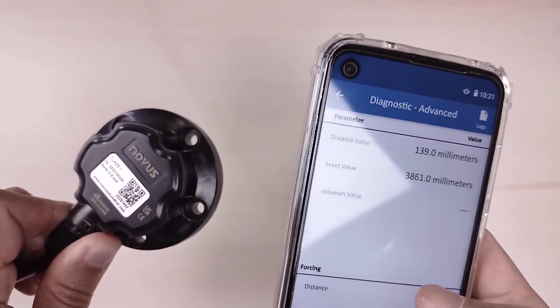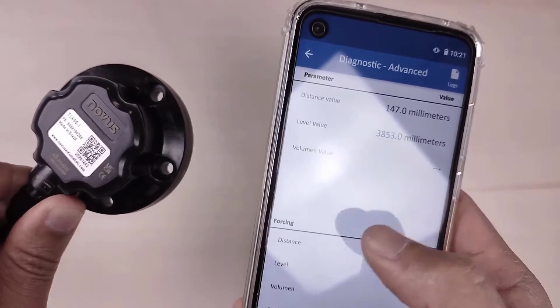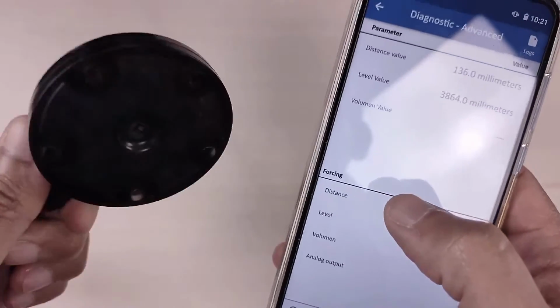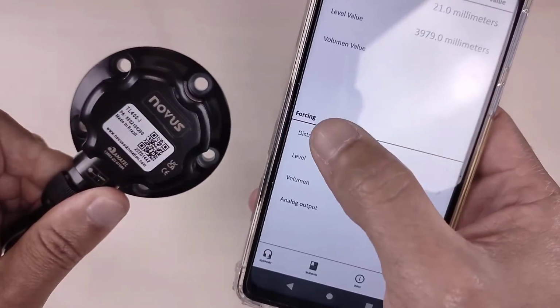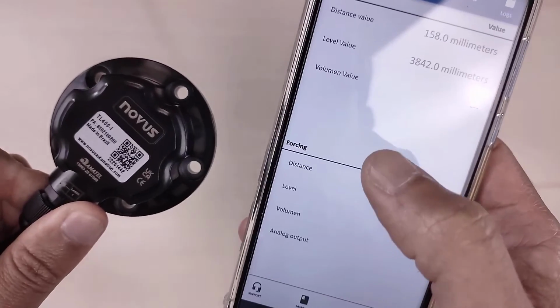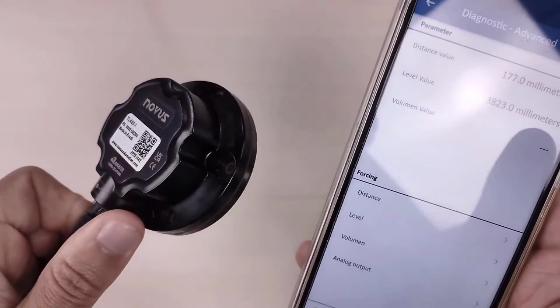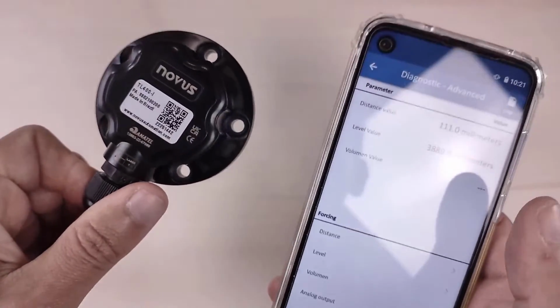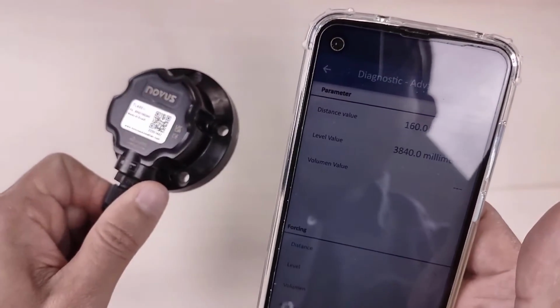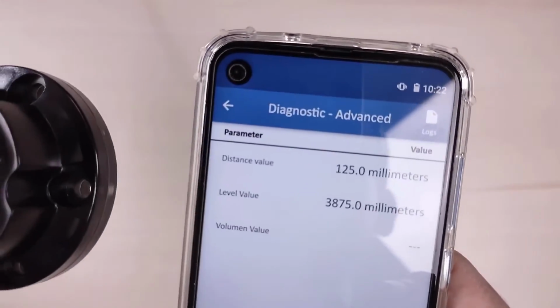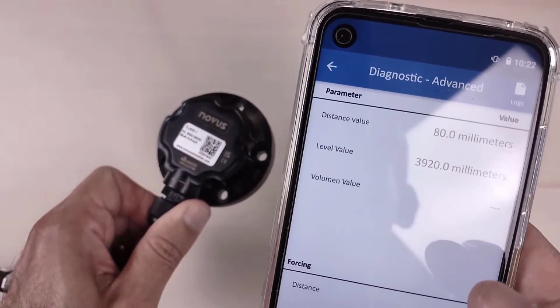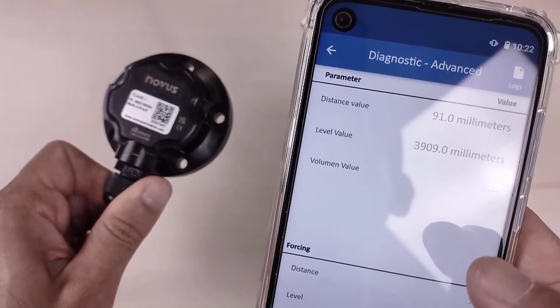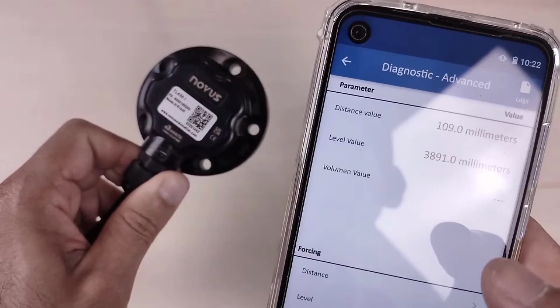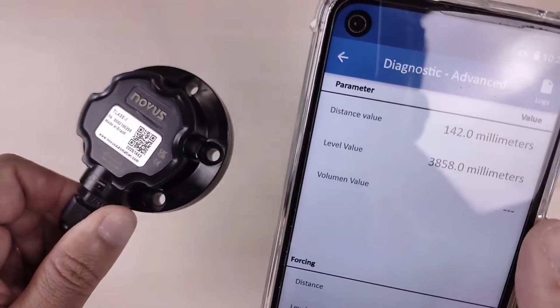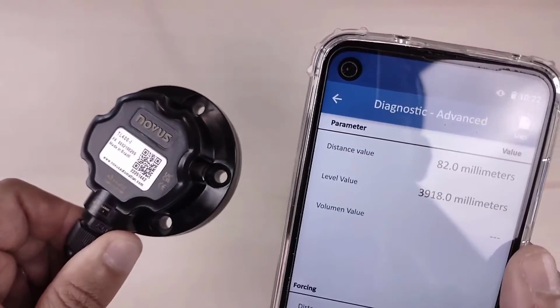You can force the output, so you can commission the transmitter with a controller or an indicator, forcing distance, level, volume, and the 4-20 analog output. So it's very, very simple, as you can see, with the update velocity of the output. Okay, that's okay.